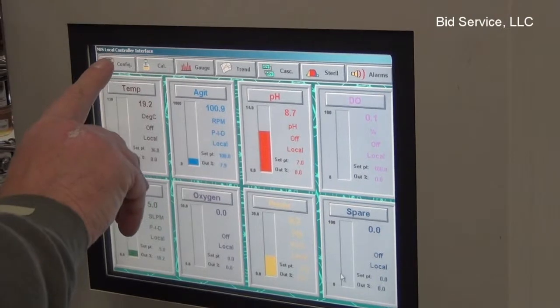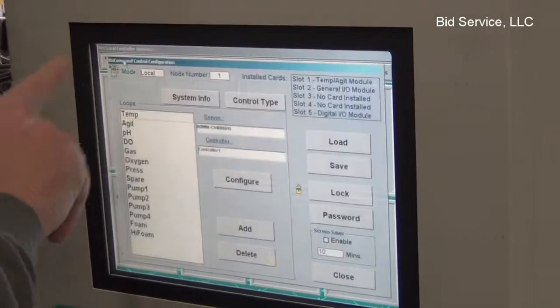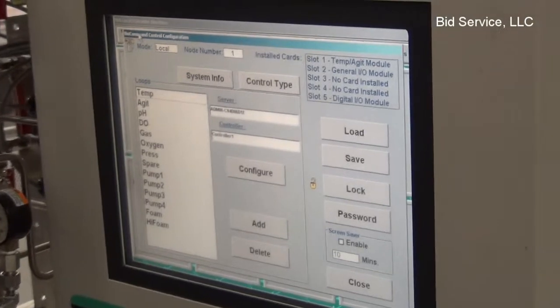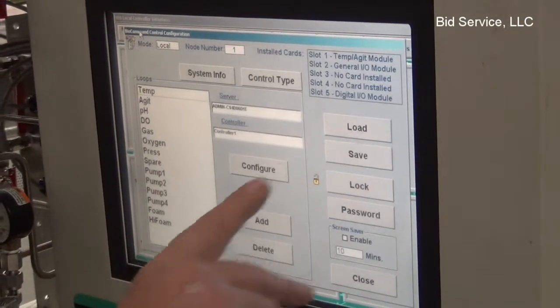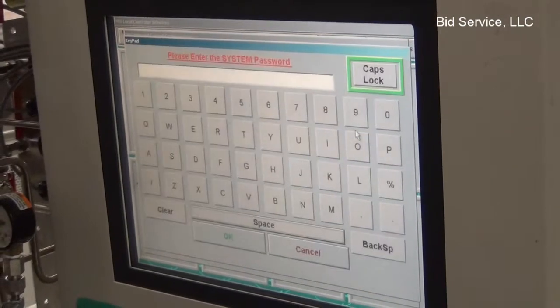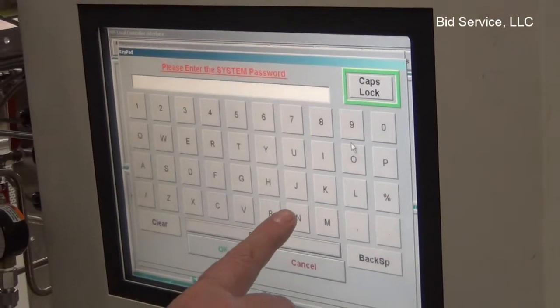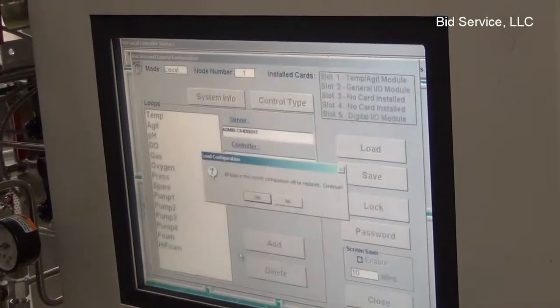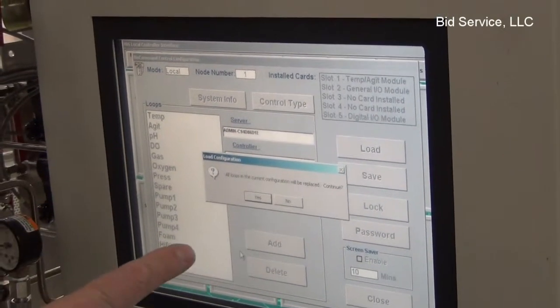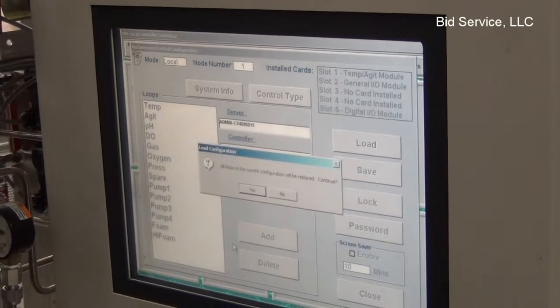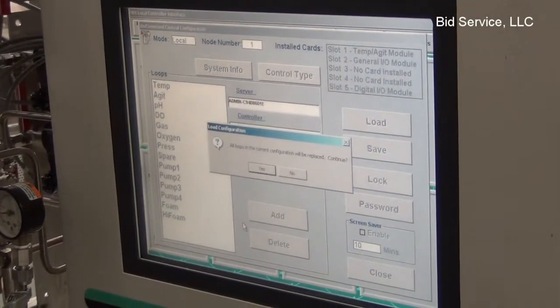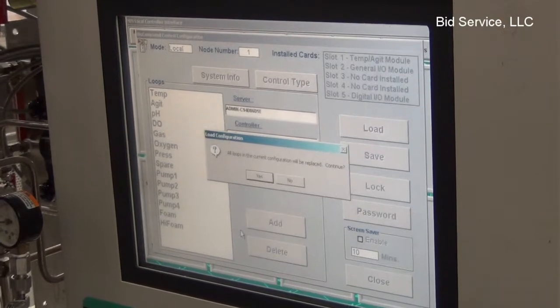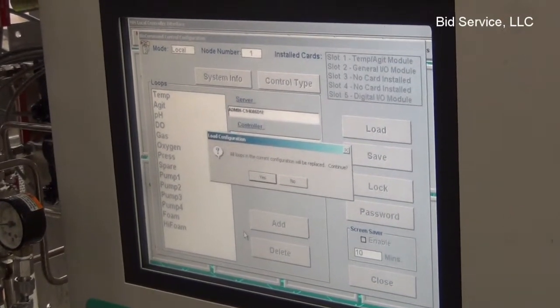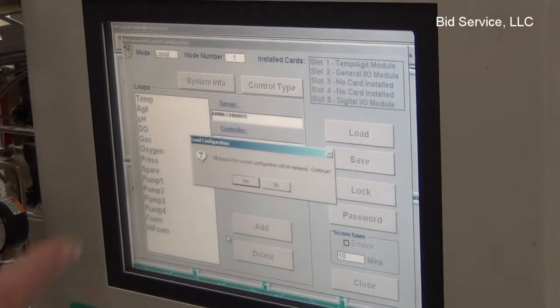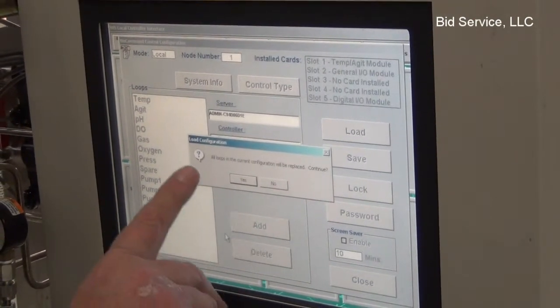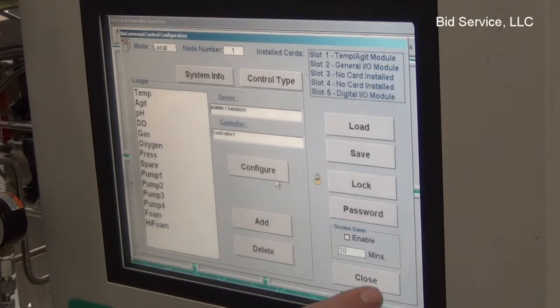If you should lose your configuration, there is a way to pull up an auxiliary configuration or a basic configuration that came with the unit. You come back to this page, you say load. It asks you for the system password, NBS, and it says all loops in the configuration will be replaced. I'm not going to continue because that will change everything that I've done so far. But it will give you a starting point again if you need to change the configuration, or if you've entered something and you can't seem to get it to work again. So I'm going to say no. We're back to this screen.